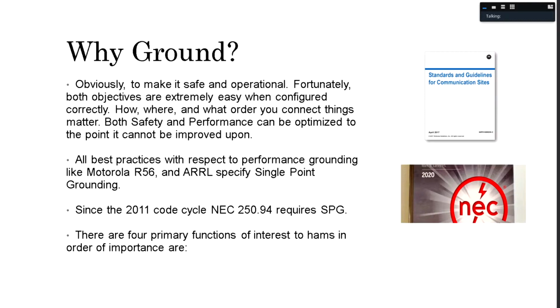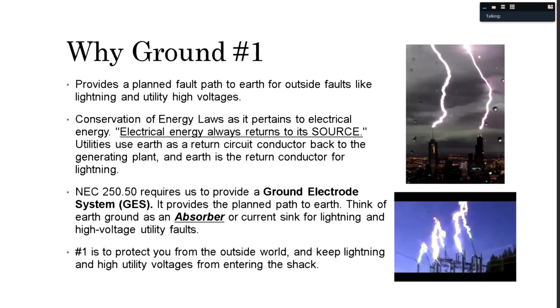There are 4 primary functions of interest to hams. Let's get started and cover them. Number 1, provides a planned fault path to Earth for outside faults like lightning and utility high voltages. Conservation of energy laws state electrical energy always returns to its source. Utilities use Earth as a return circuit conductor back to the generating plant, and the Earth is a return conductor for lightning. NEC 250.50 requires us to provide a ground electrode system. It provides a planned path back to Earth. Think of Earth ground as an absorber or current sink for lightning and high voltage utility faults.